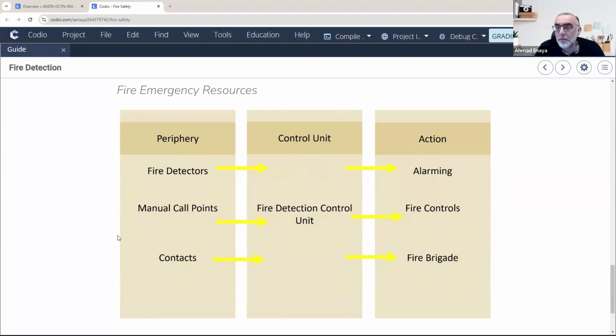even without power. Even the alarm should be somehow connected to UPS or maybe some additional power sources to make sure it is not affected by the outage of power, because it is typical for fire to be initiated by power failure or maybe a power malfunction, and then the first thing to be affected is the power system. So these alarm systems should function without the commercial power, without the normal power in the building. They should have their own backup power, or maybe a DC powered or battery powered system.